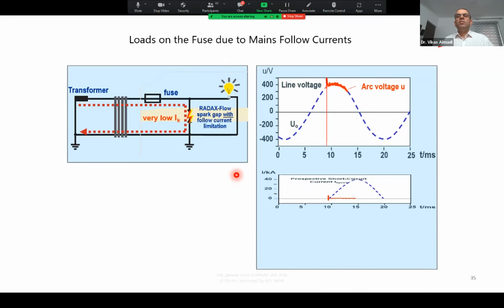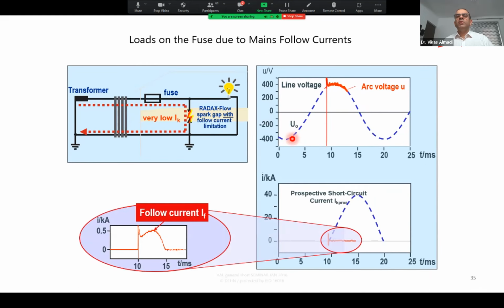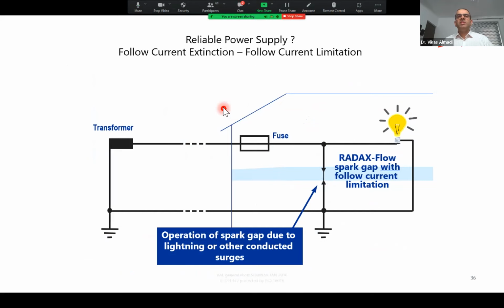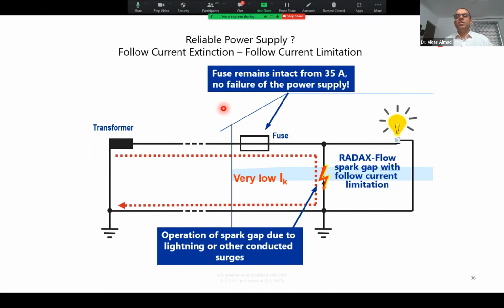So here, if the total current which would have flown through the SPD is like this, but the SPD has a suppression system, so it suppresses the current to this value. That means the overall wave shape of the sine will not be disturbed too much, and the load will always be on. So if you suppress this current, which is created by the lightning, by the operation of the SPDs, the fuses will not blow or trip, and then you will get continuity of the services.